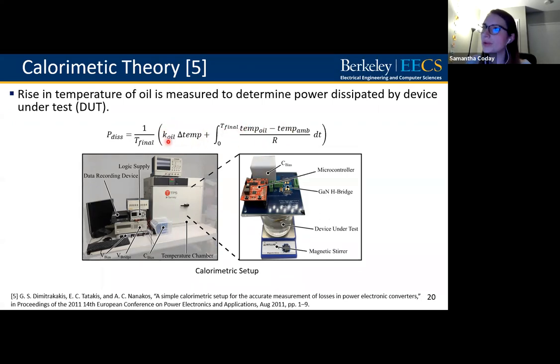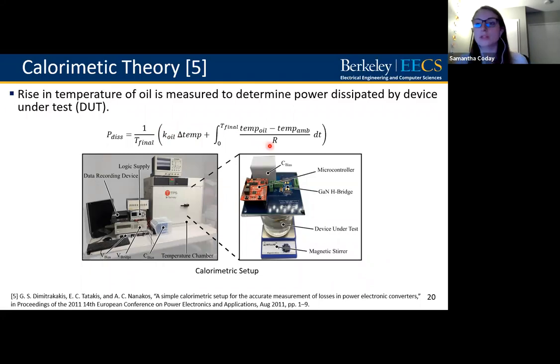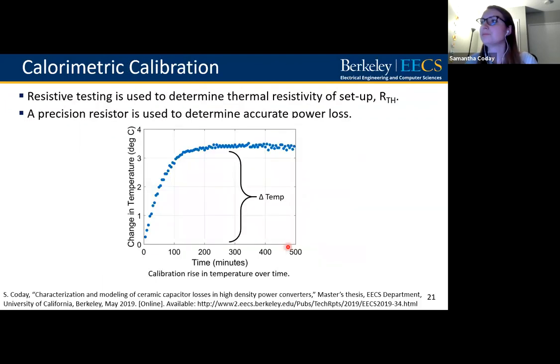I already talked about this K oil factor. The last big part of a calorimetric measurement is to understand the thermal resistivity of your setup. Pretty much that means how much heat is escaping from your setup just because it's not thermally isolated enough. And actually, not shown here, we wrap this in some thermally insulating material to try and increase our thermal resistivity.